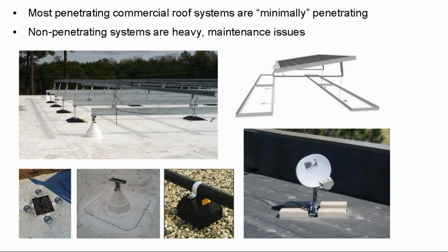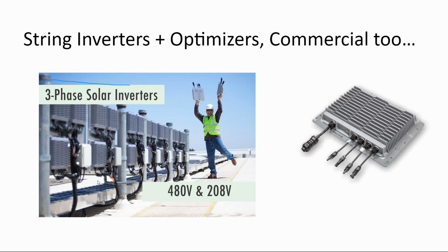And so that's why on rooftops there are cable management solutions either integrated into the railing, or ultimately you need to get cable tray to carry that cable back along the rooftop. And cable tray can be surprisingly expensive. So it can be very tempting to say, well, let's not do cable tray. Let's just carry all the cable out from the edge perimeter and put it into conduit.